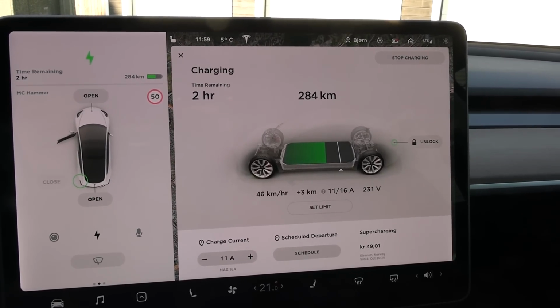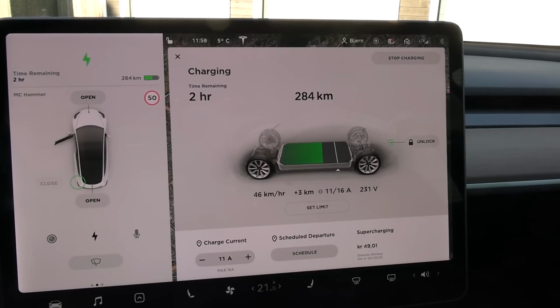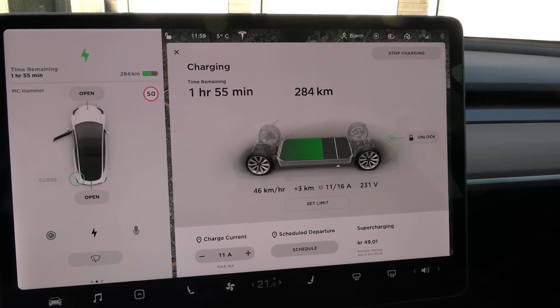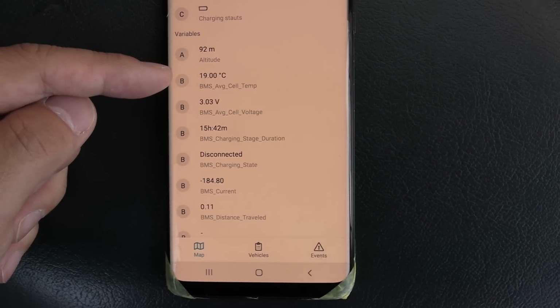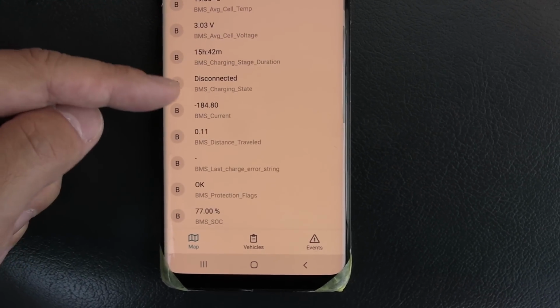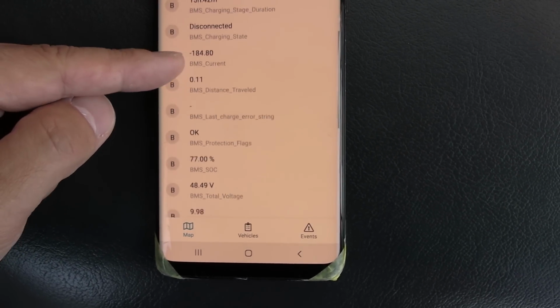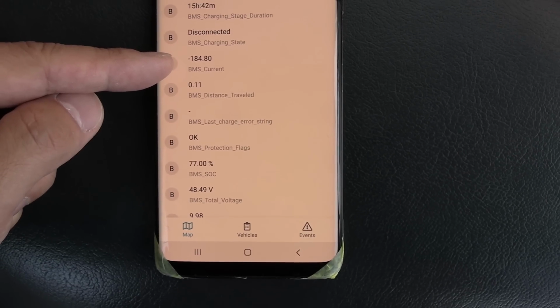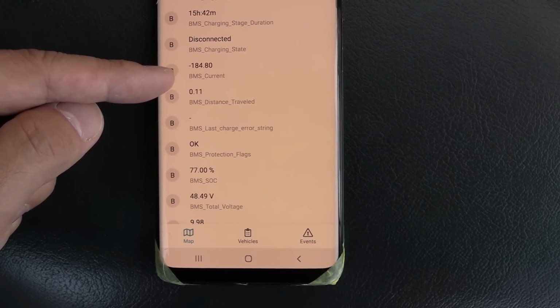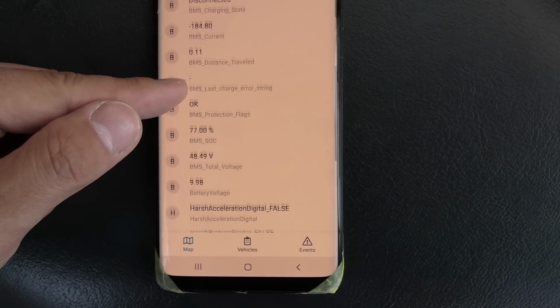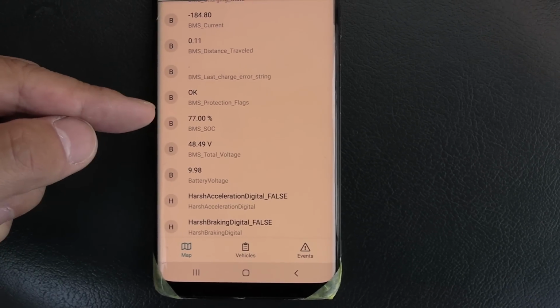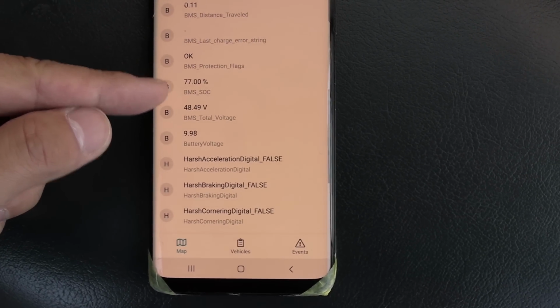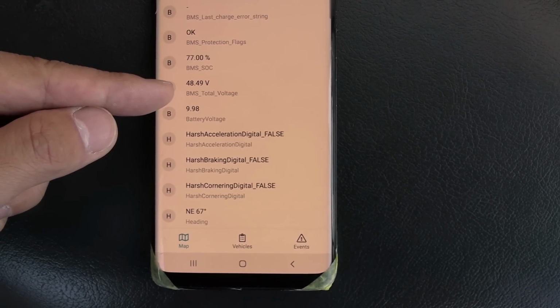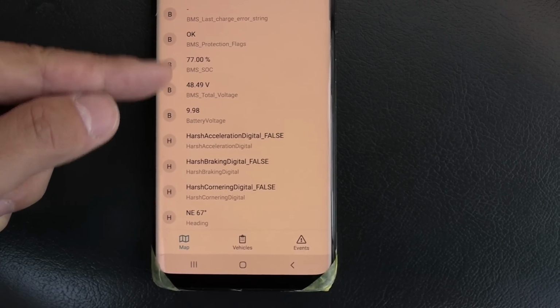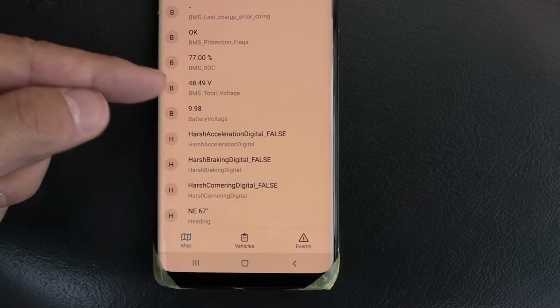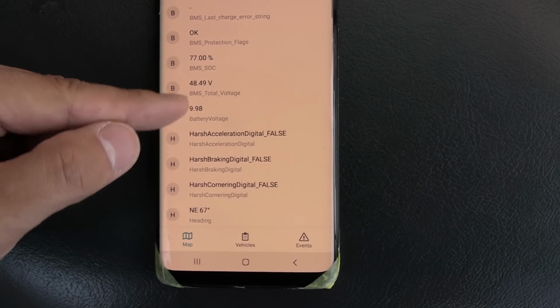Let's run it for a little while because I want to see what happens with the temperatures. We are at 19 degrees Celsius, and the BMS is pulling roughly 185 amp, plus or minus a little. We're down to 77%, and the voltage has dropped a little bit because we are pulling current, and also we are discharged to 77%.